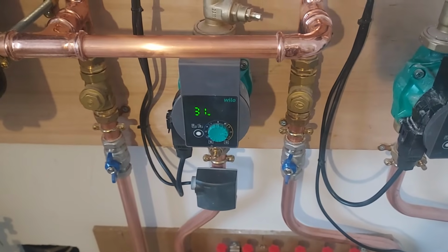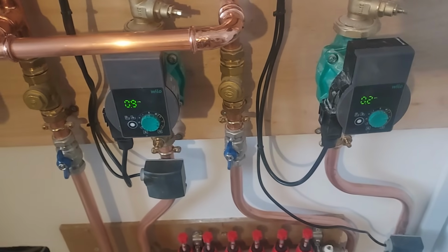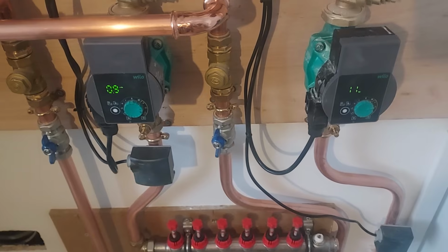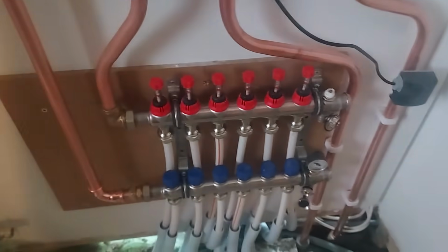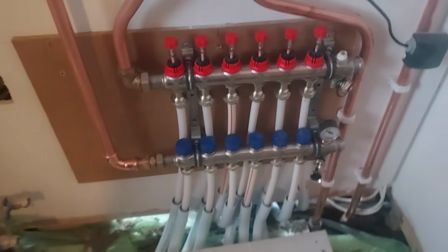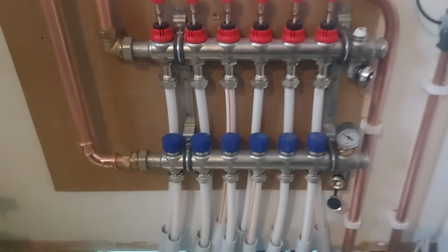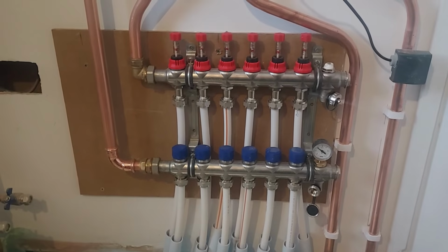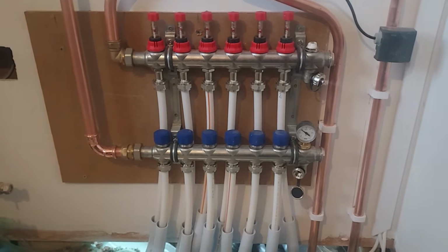Now, with the meters head, we can make a little bit of a judgment of where we might be between the tenths of a cubic meter per hour reading. But we're going to get fairly accurate balancing by going through this. This is an Ambient manifold. I've started to use Ambient because they have a guy there who seems to understand the design criteria needed for underfloor heating quite well, and gives us access to him.